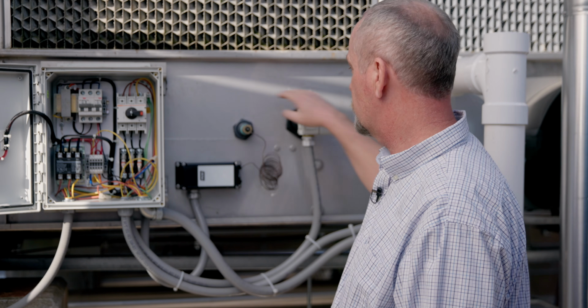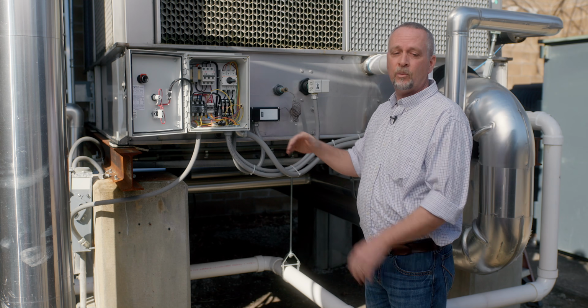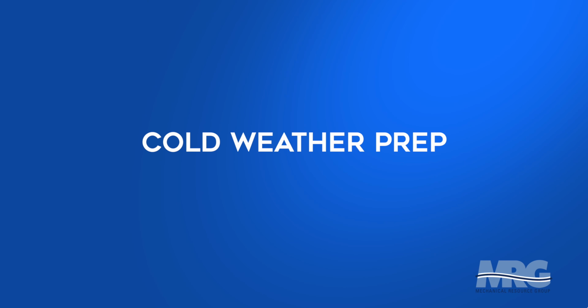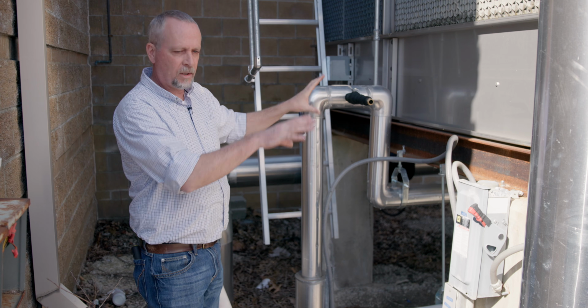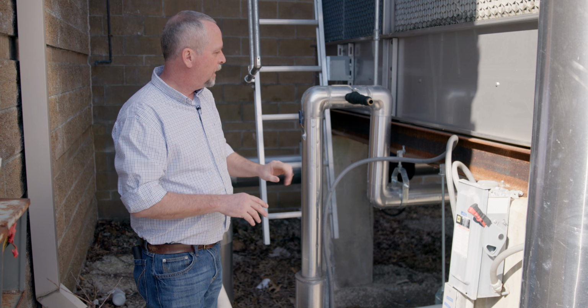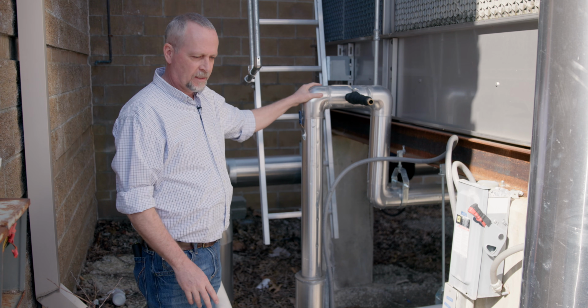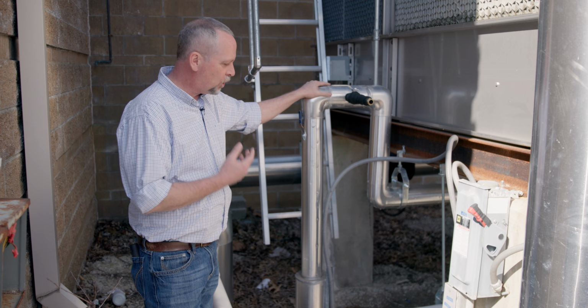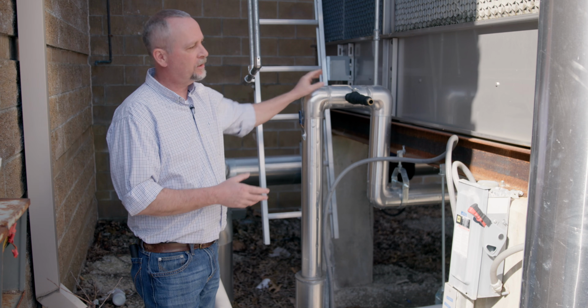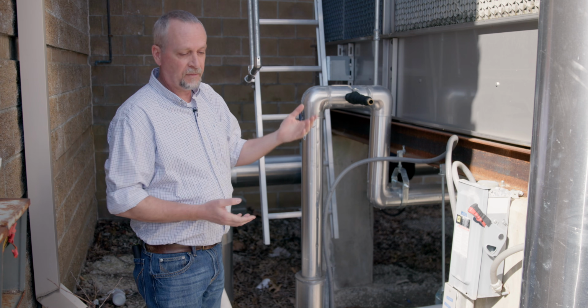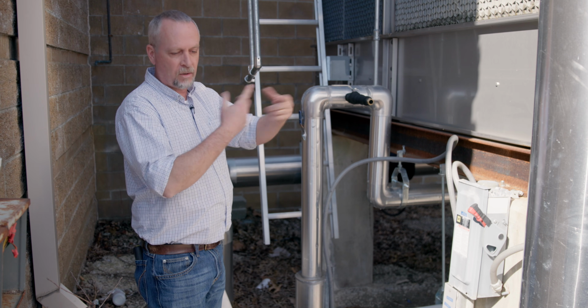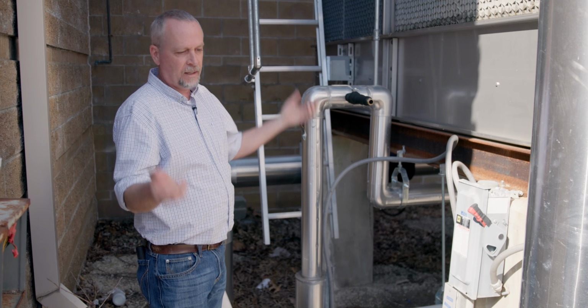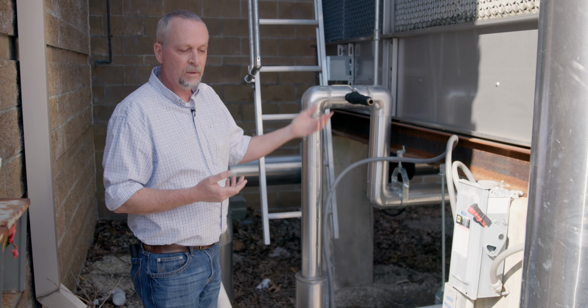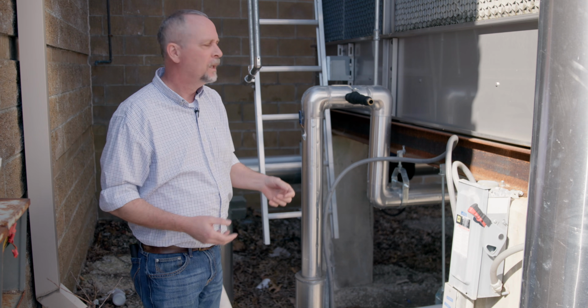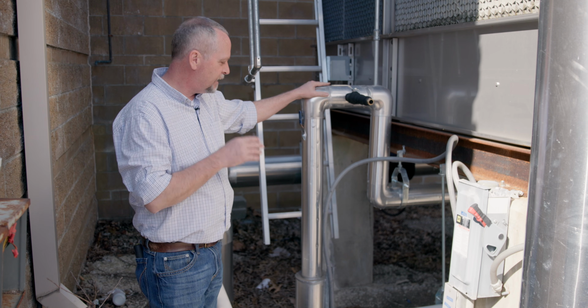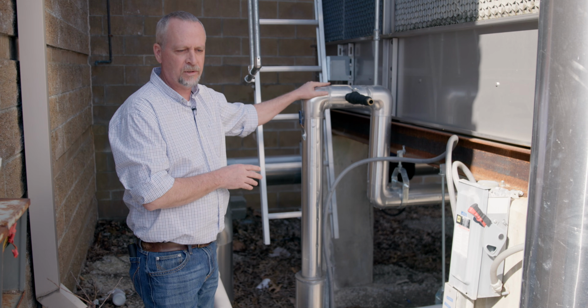We talked about making sure we've got water for our heater, but how do we maintain the proper water level? Now, we talked about our basin heater keeping our cold water sump from freezing. But we've got this external device that is field installed, which is called our cooling tower makeup water line. So basically, when my tower sump starts evaporating water, which is normal, we're running heat across this thing, circulating the water, pulling outside air across it, we're going to lose some water to evaporation. We have to replace that water with what's called cooling tower makeup. This is the most common failure we see on these cooling towers in the wintertime.